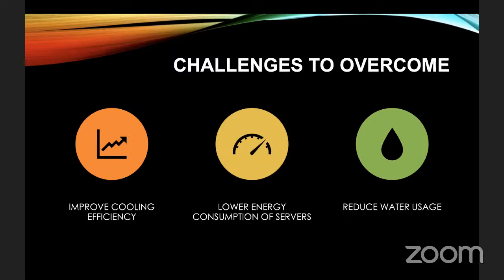So the same thing happens. If you pass this cold water through the servers, it will actually carry away more heat. But obviously water and electricity don't mix. So how do you do this? Well, you use something called dielectric fluids. These are engineered fluids that are non-conductive, and you can submerge the servers inside of this fluid. Basically the servers will boil the liquid, and as the liquid boils, it evaporates and carries that heat energy away with it to a condenser, where it condenses back to a fluid and is pumped back to the servers. So it goes through a closed loop system, and this is called two-phase liquid submersion cooling, because you're going through two phases of the fluid. You're going from a liquid to a gas.